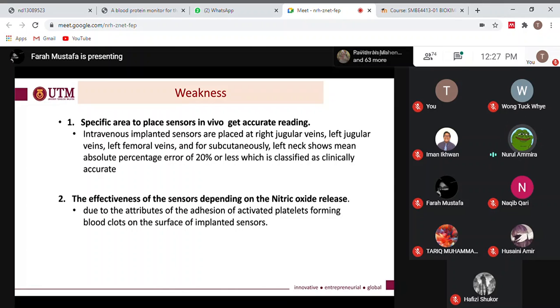And when it is exposed to the internal environment, such as the moisture and the body temperature, the nitric oxide released through the catheter housing will also result in anti-platelet or anti-thrombotic activity that can prevent thrombosis or fibril formation at the sensor site. But when the catheter housing stops releasing the nitric oxide, the output reading of the sensor will change significantly, and the reading cannot be used anymore due to the adhesion of activated platelets forming at the sensor placement surface. So after 7 days of nitric oxide decrease, it will affect the performance of the sensors.